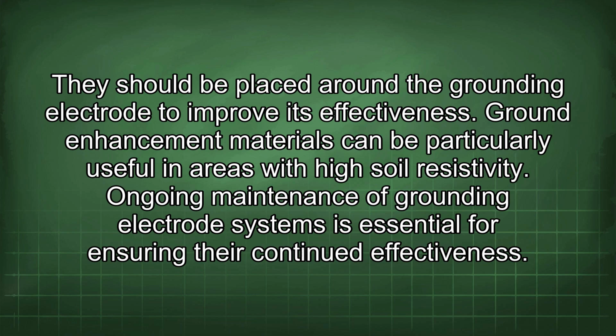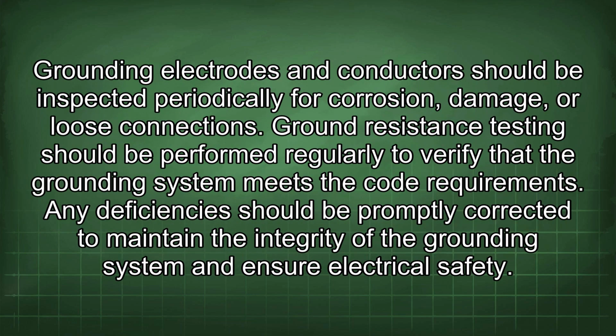Ongoing maintenance of grounding electrode systems is essential for ensuring their continued effectiveness. Grounding electrodes and conductors should be inspected periodically for corrosion, damage, or loose connections. Ground resistance testing should be performed regularly to verify that the grounding system meets the code requirements. Any deficiencies should be promptly corrected to maintain the integrity of the grounding system and ensure electrical safety.